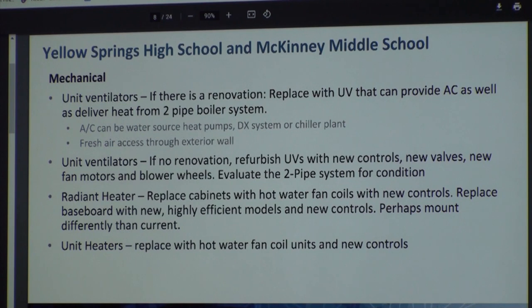Does it provide enough air turnover in the room? Yes, but you'd have to modify it for fresh air. Each of those unit ventilators is on an exterior wall, so you'd cut out a section of brick and put a louver and a sleeve in there to pull fresh air in. You size the unit ventilator for the room, and universities use unit ventilators that last literally forever.